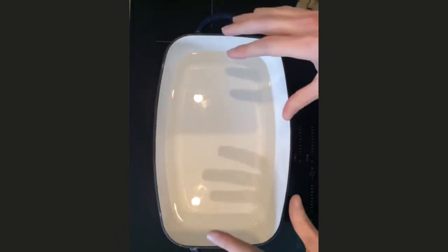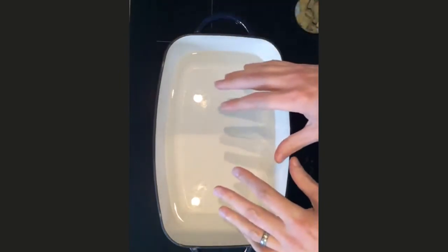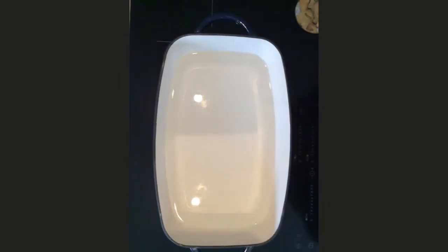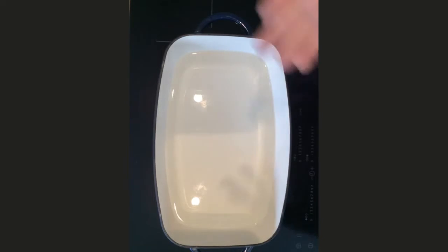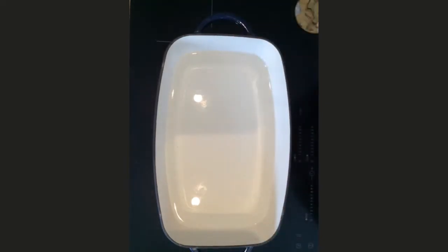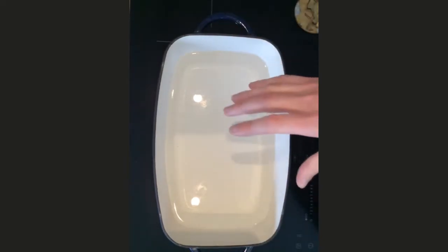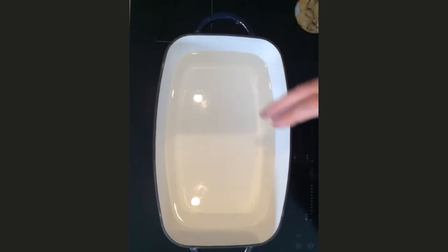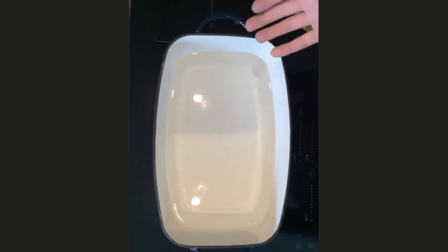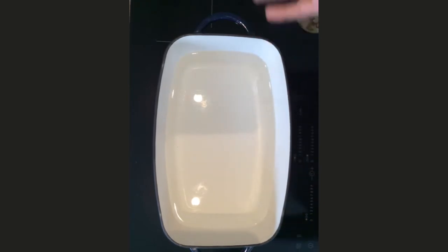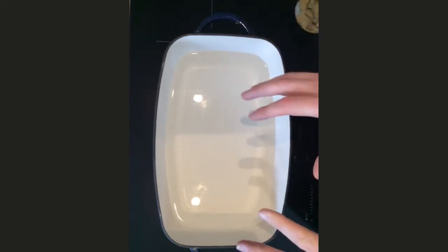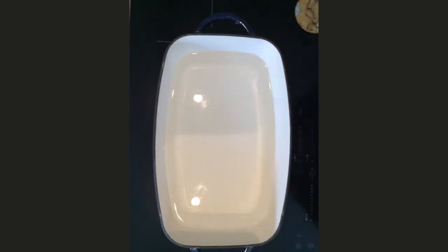So I've got a bowl here of hot water, and I'm going to be dunking some sprinkler heads into the water, and you can see the reaction. I don't know what the temperature of the water is, but it's hot water, so I'm hoping it's above 68 degrees. Otherwise, it won't work. And it's obviously not hotter than 100 degrees. It is hot water, but it's not boiling water.